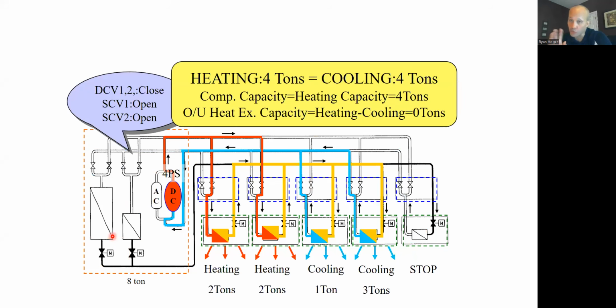And then if I can get it so there's a certain moment in time where it's exactly even, 2 tons of heating, 2 tons of cooling, this guy doesn't need anything, great. I'm going to operate my compressor at 4 tons. I'm going to shut off all the coils outside, shut off the outside fan, and I'm just going to circulate heat between the zones, the ones that want it and the ones that don't. This doesn't happen very many moments in time, but conceptually, just to give you an idea.